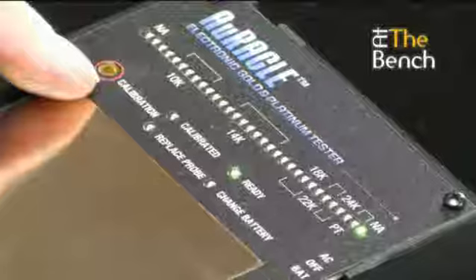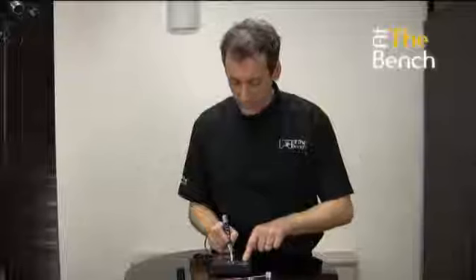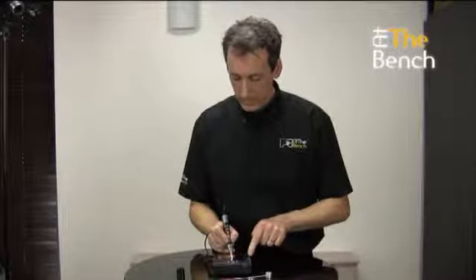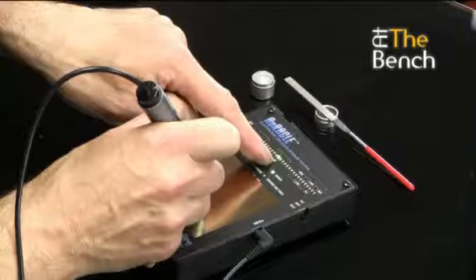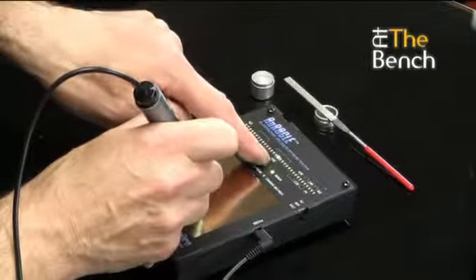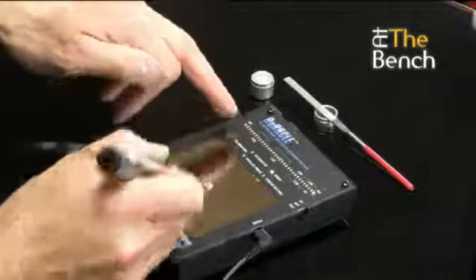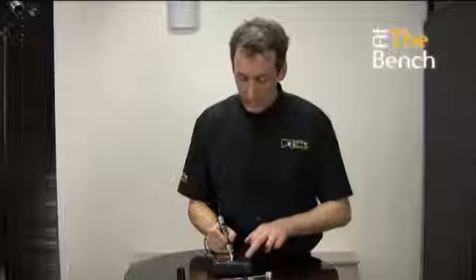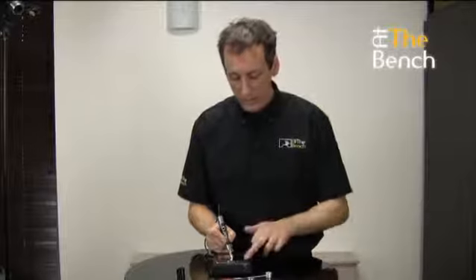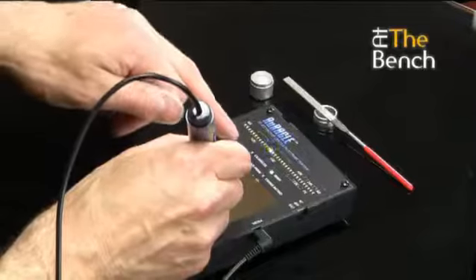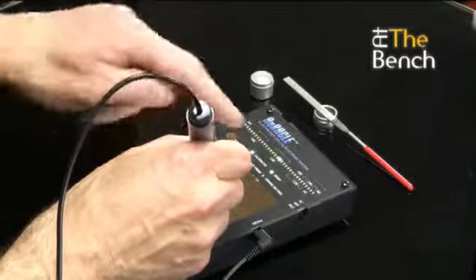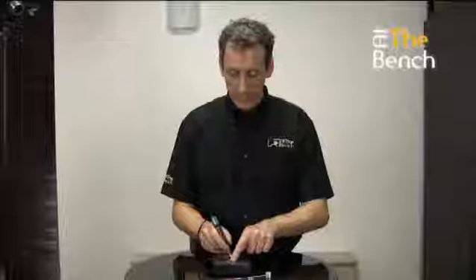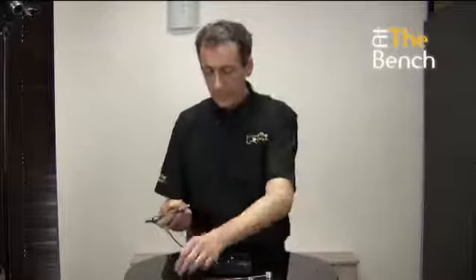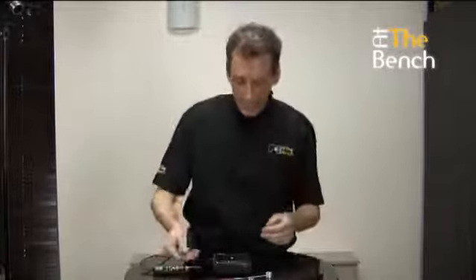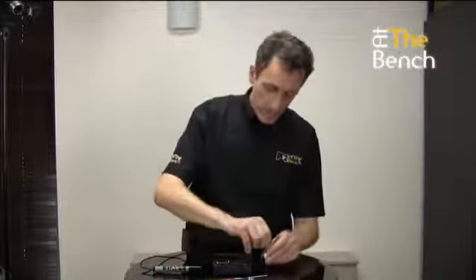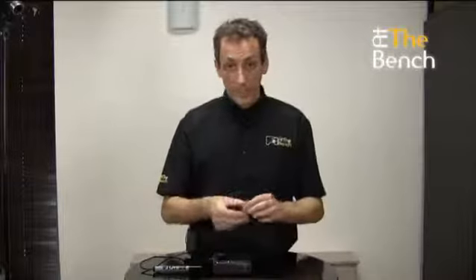And what we need to do is to push the calibration button here on the side. And it should light up exactly right in the middle where it says 14 karat there. If it doesn't, come along, take the probe off, put it back on, and sometimes you may have to do this about 3 times. And the 14 karat light lights up. So now the machine has been successfully calibrated. We'll put our little piece back away, save that for the next time we come to calibrate it.